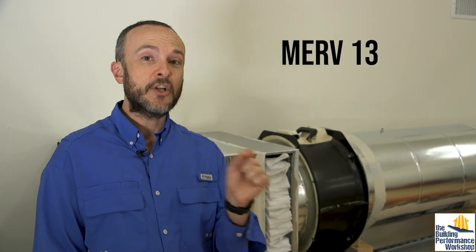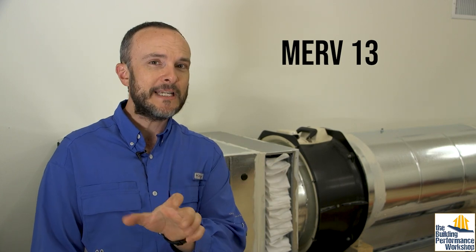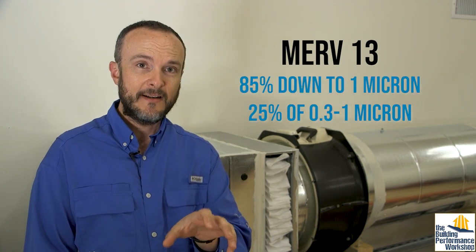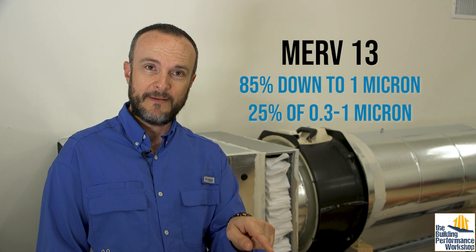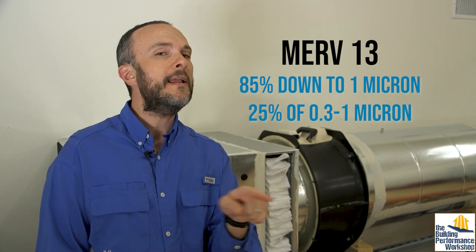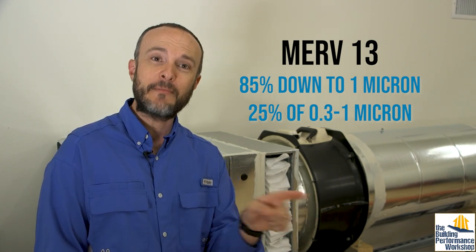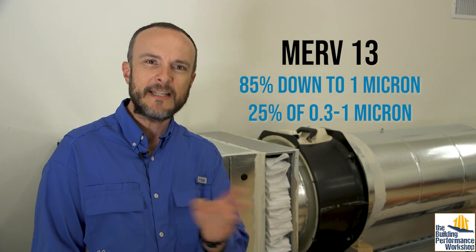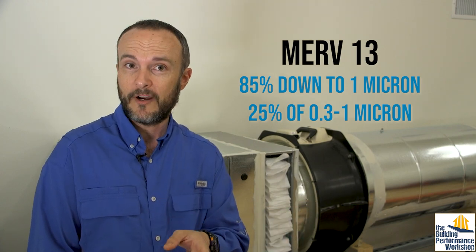Once you get to MERV 13, that's where you start really tackling those smaller things. So MERV 13 is going to tackle 85% of the particles down to one micron. And it's also going to grab 25% of the particles that are smaller than that, about 300 nanometers to a thousand nanometers, which is one micron.